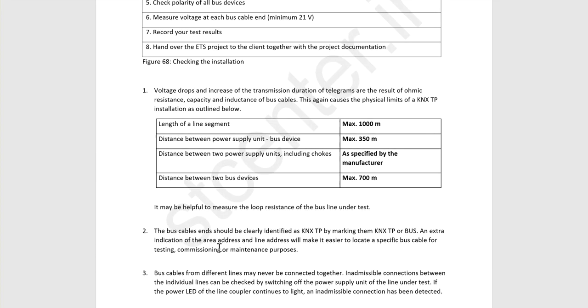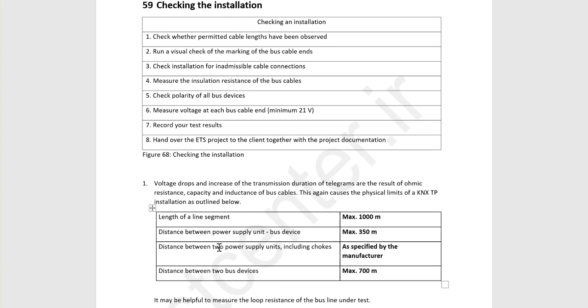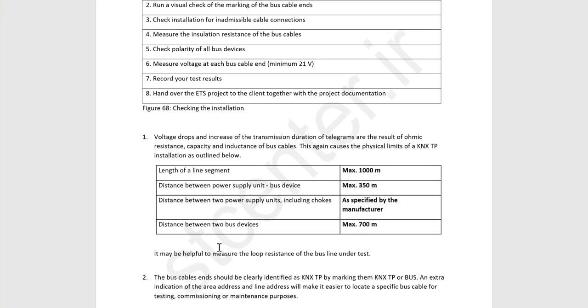And remember, do not connect to any bus when you want to make this measurement. Your bus devices should not be connected. Of course, the connector and the cable should be connected to each other, but you should separate the connector from your bus devices, because if you apply 240 volt DC to the KNX devices, they will be burned.